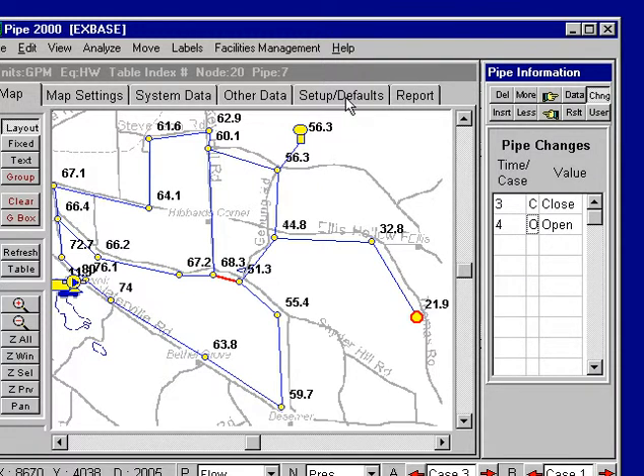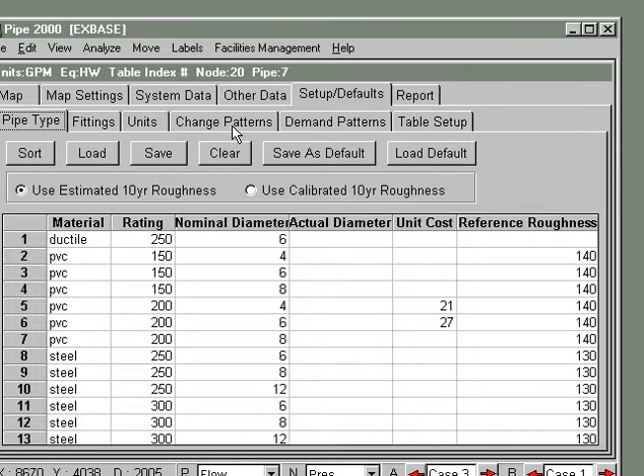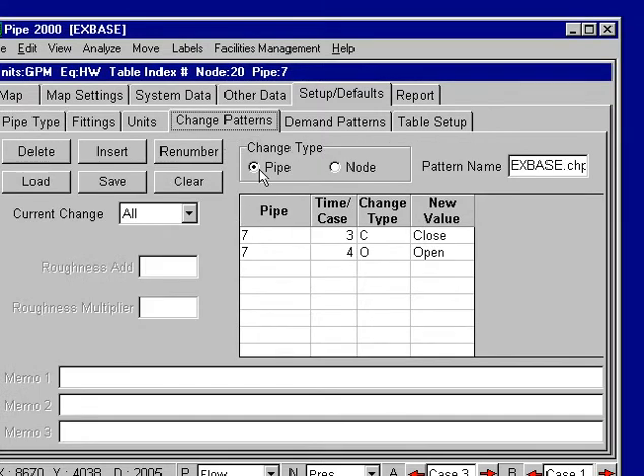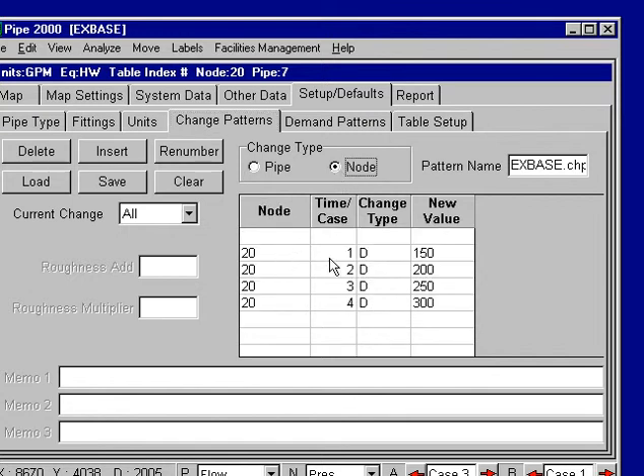All the changes are summarized under the Setups and Default Change Patterns screen. We can see for pipes the changes I put in — pipe number 7 in change 3 was closed, and change 4 was opened. Node number 20 had the demand changes we set up. The change patterns can be saved under names we give them, and we can reload these change patterns for other simulations as long as we use the same baseline data with the same node and pipe numbers. The changes give us a lot of flexibility for running additional regular simulations or for making changes during extended period simulations.